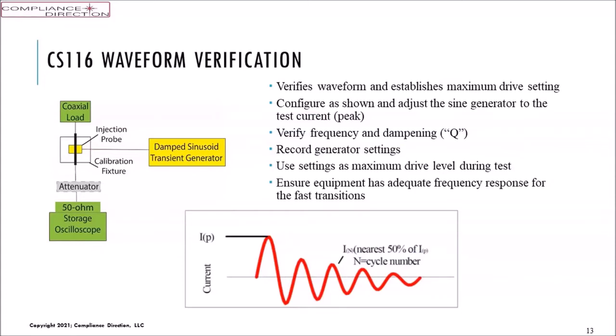For CS116, we do a similar thing, except now we're going to verify the maximum to be applied. So we measure the applied current. If we get to the current before we get to the maximum setting, then that's what we use. If we go to the maximum setting, we record what current was produced. We need to verify the frequency and the damping, or the Q. The Q is how quickly the waveform dampens from a peak current to the midway point. And that relationship, using the formula that's in the standard, should be 15 plus or minus 5.